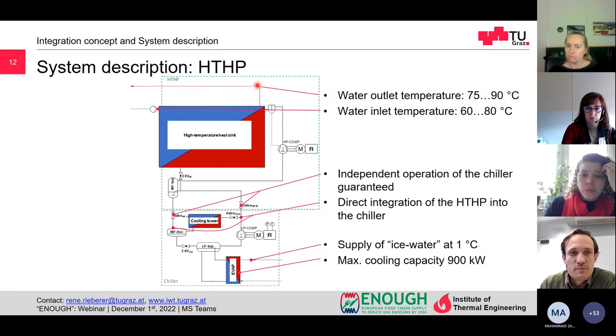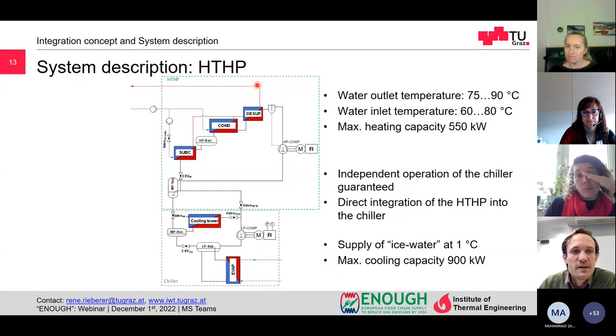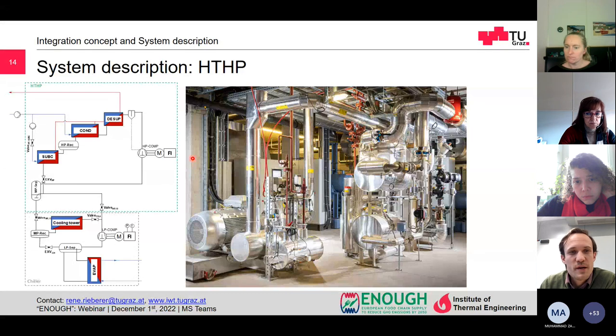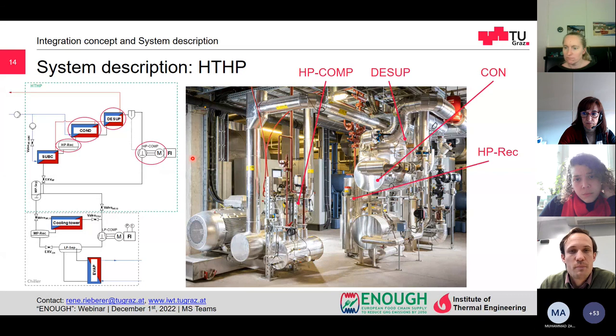The high temperature heat pump was not as simple as it is shown in this figure here. It consists of a desuperheater, where the refrigerant is desuperheated, a condenser, where the refrigerant is liquefied, a high pressure receiver, and a subcooler. I also have some pictures here of our high temperature heat pump. You can see it here with the high pressure compressor, the insulated desuperheater, condenser, high pressure receiver, and the subcooler.